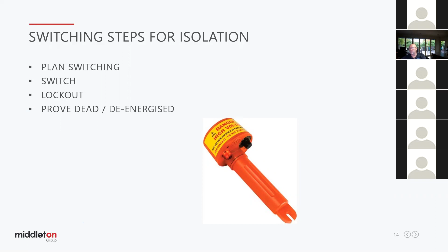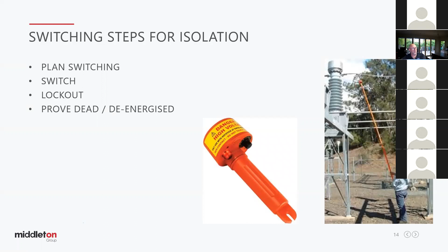A couple of things to note about using a tester: the process is always—test that the tester works properly, undertake the test that the conductor's de-energised, then test the tester again. Some testers have a self-test function that can be used, but it's always important to test, do the test, then test the tester again to make sure it's working properly.